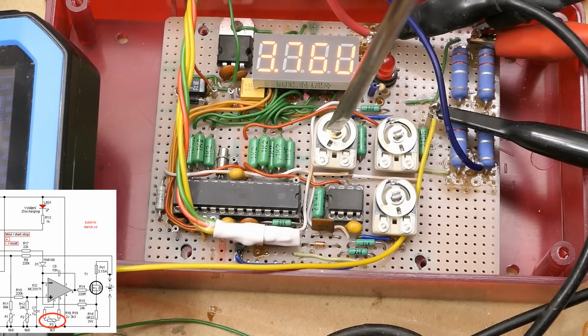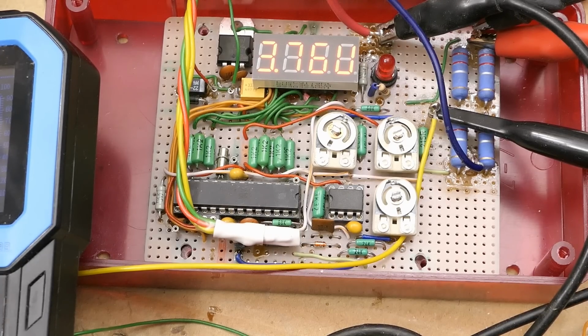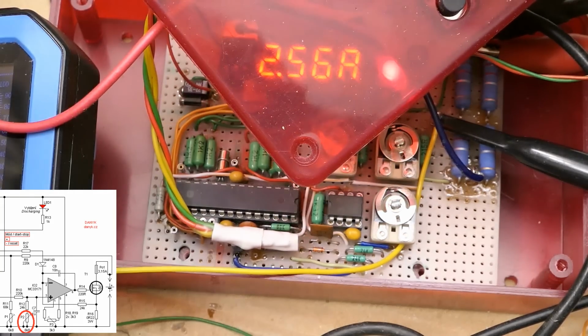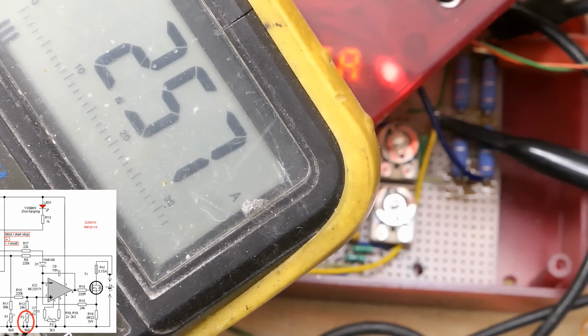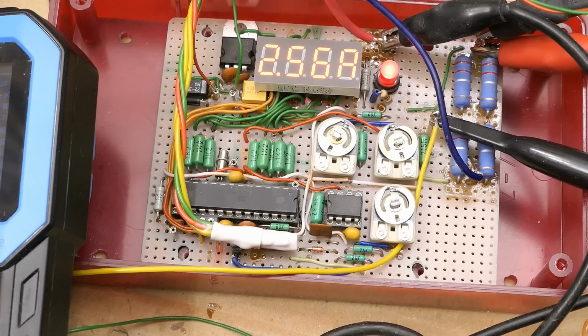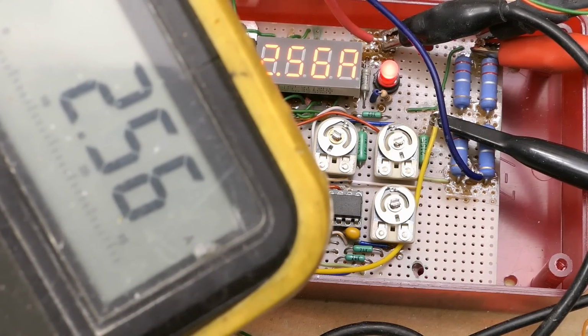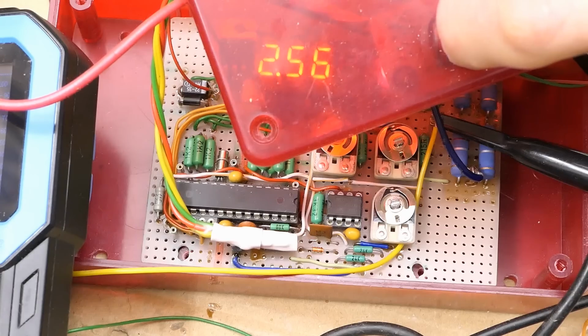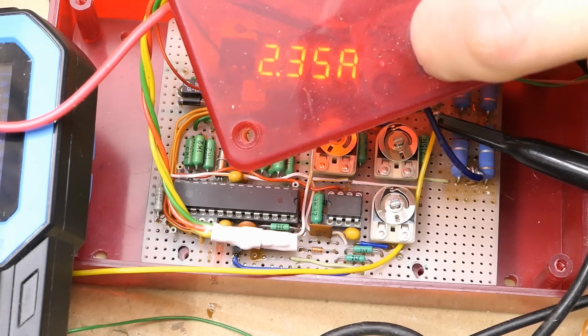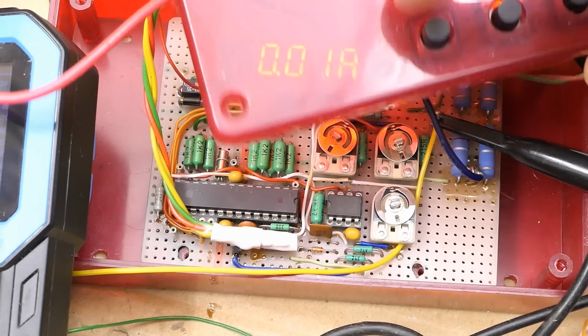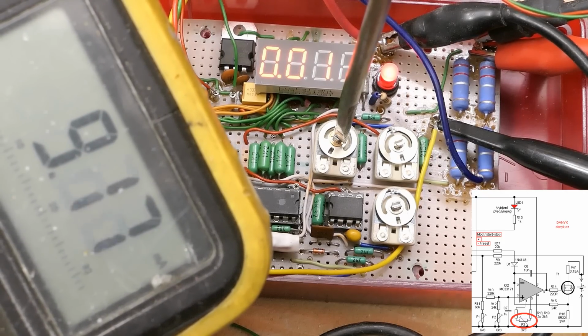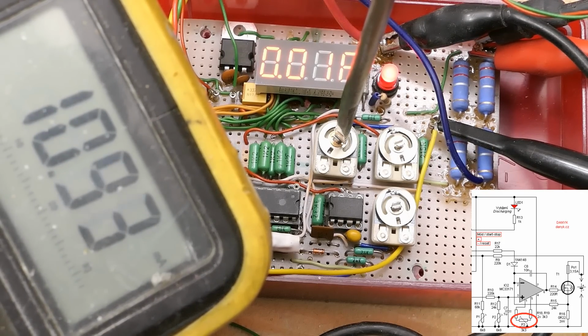You start with setting the offset potentiometer to the middle of the scale. Then you set it to the maximum current, 2.56 amps, and you're using a battery or a power supply capable of more than 2.56 amps. And you adjust the current potentiometer, so the actual current is also 2.56 amps. And of course the current meter is in series with the positive or the negative battery terminal. And then you go to the lowest current, 0.01 amps. You set the offset potentiometer, so it's actually 10 milliamps or 0.01 amps.